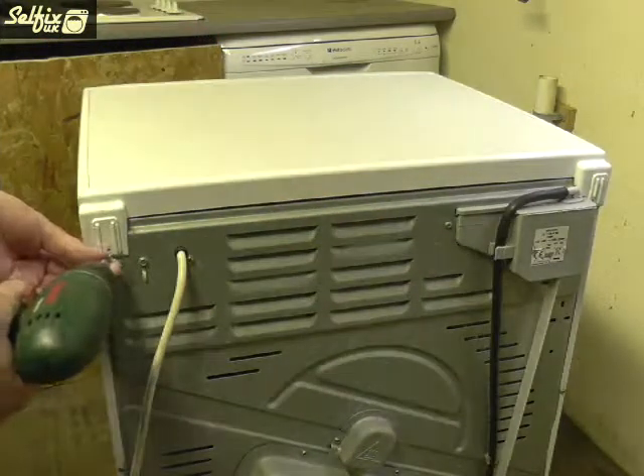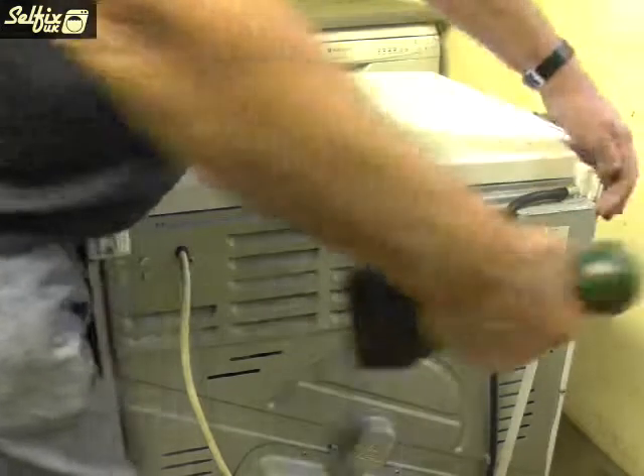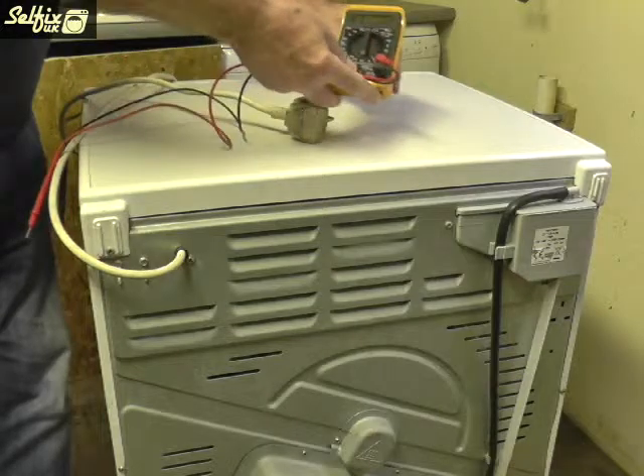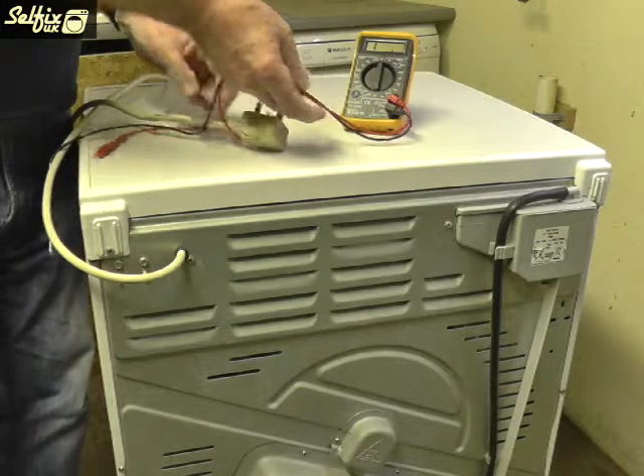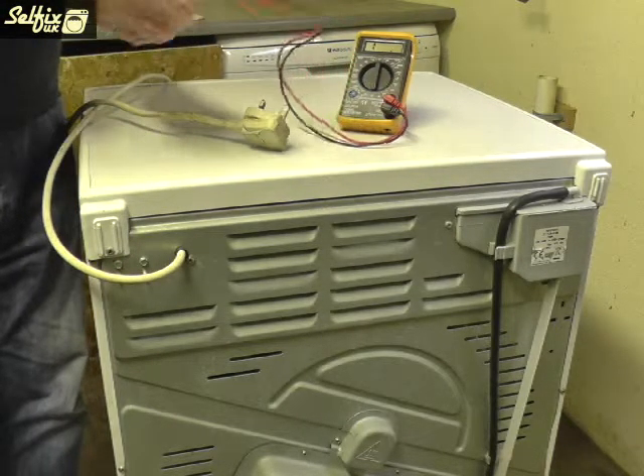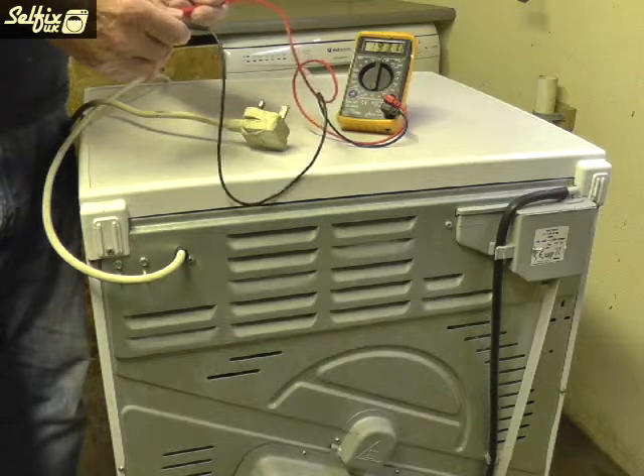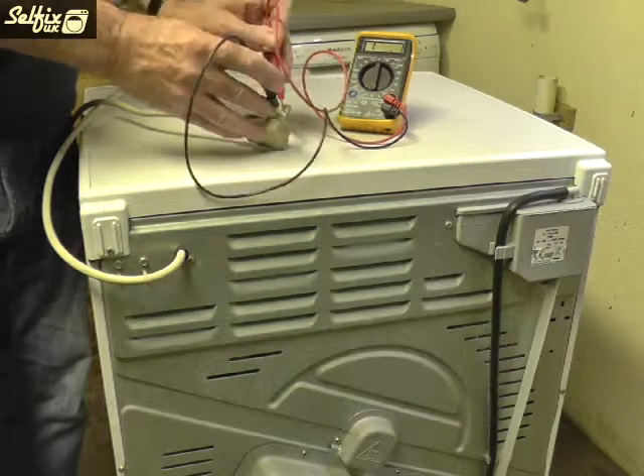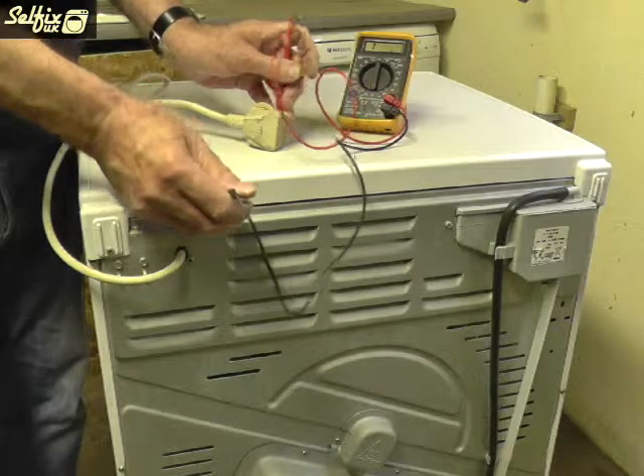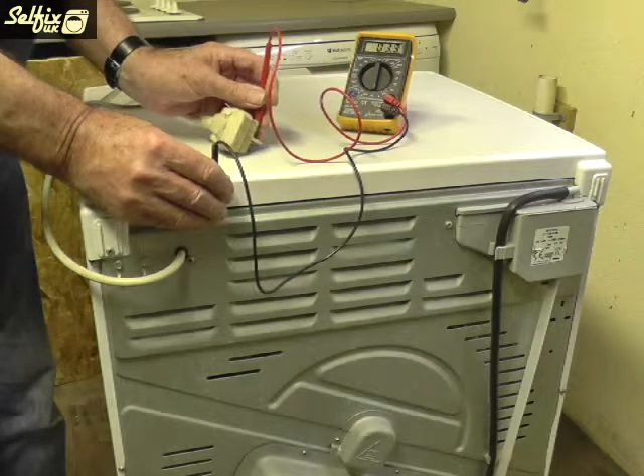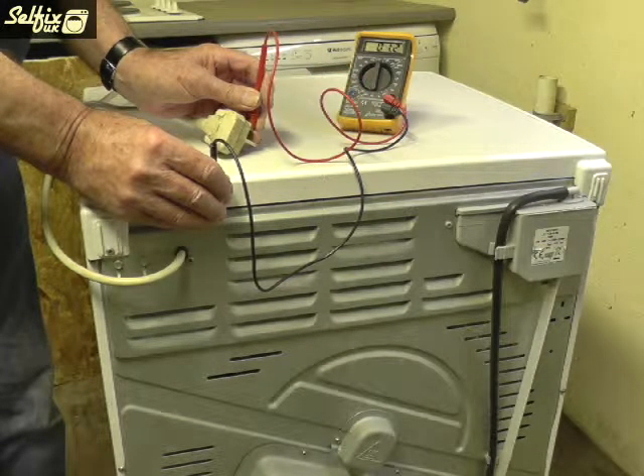But before you connect it up, take a minute to do an earth continuity test. Set the dial to 200 and attach one probe to the earth on the mains plug, whilst touching any exposed part of the cabinet with the other probe. You should get a reading of about 0.5 ohms, but as long as you get a reading, then you should be fine. However, if there is no reading, you may want to take another look at the machine, because you've got no earth.